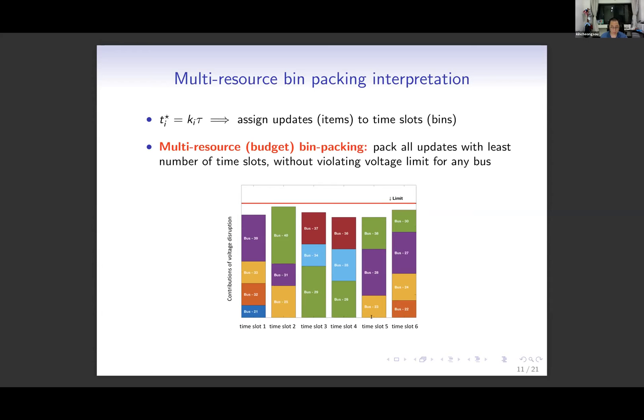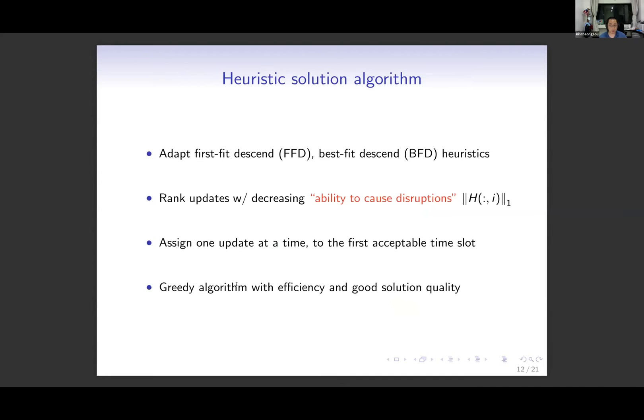We call our problem the multi-resource bin packing problem with a budget, because we have more than one bus for which we need to enforce voltage limits. The bin packing problem is classical, with many well-known heuristic algorithms such as First-Fit Decreasing (FFD) and Best-Fit Decreasing (BFD). We make a slight modification to these algorithms for our multi-resource case. These heuristic algorithms turn out to be very effective for our application, as we'll see in our case study.